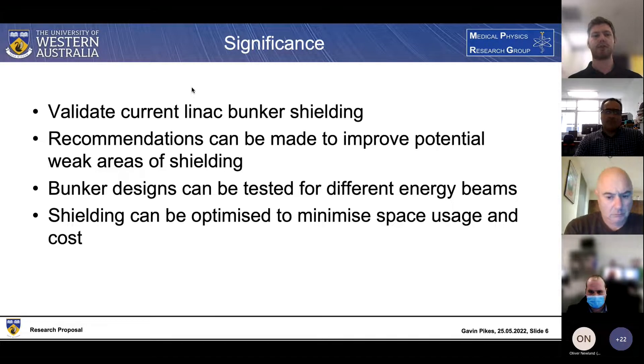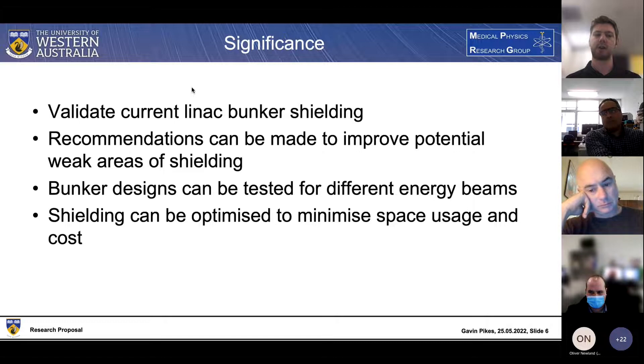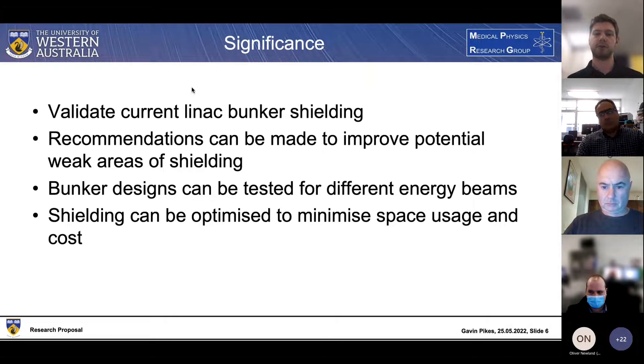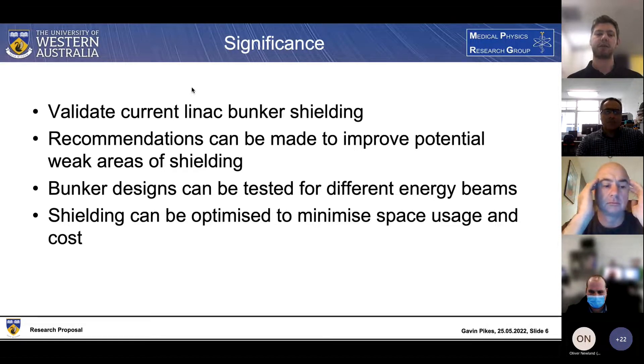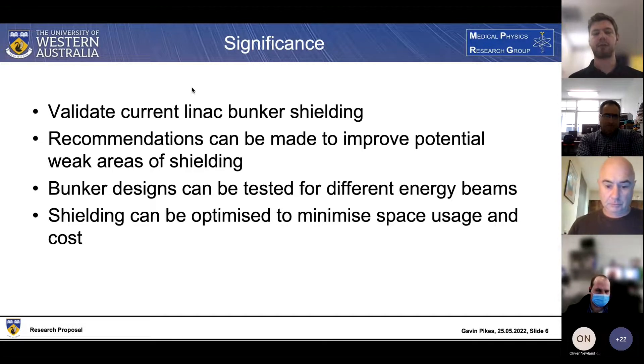The significance of my project: first, we're able to validate current linac bunker shielding, ensuring the bunker is working as intended and there isn't exposure to surrounding rooms. If there are any weak areas we can look at methods for improving those - say a secondary barrier is too thin, we can increase the thickness to reduce exposure to the next door room. We can also test different bunker designs with different energies, say a bunker designed for a 6 MV beam tested with an 18 MV beam, as well as optimizing space and cost usage.